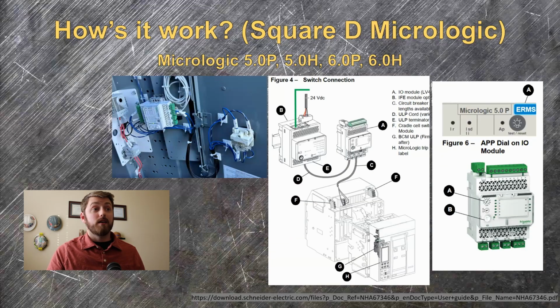Square D's other system, which they differentiate by calling it ERMS, does the same thing, except to get the signal to some of their micrologic trip units, there's an IFE communications module to send the signal to the trip unit over Modbus instead of a direct 24 volt input. I don't know why they do this, because 90% of the time it's a single maintenance mode switch for a single breaker. But I guess it makes it easier to add stuff to the system later or do monitoring, things like that. It only works on trip units that have this blue ERMS label on them.